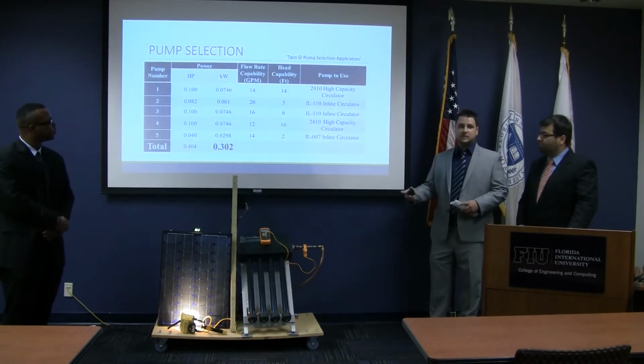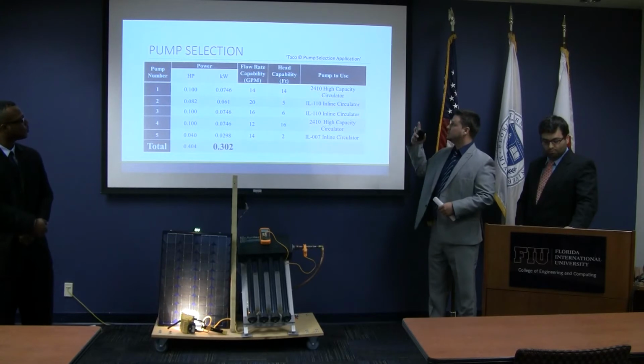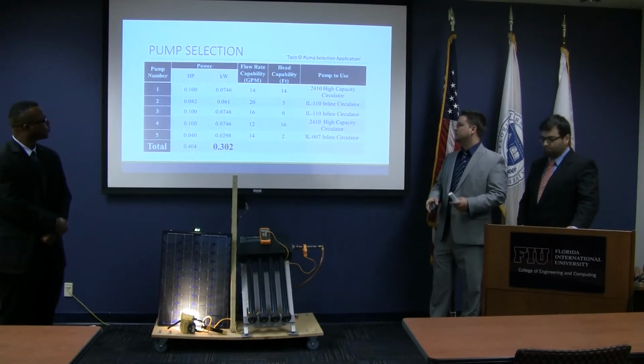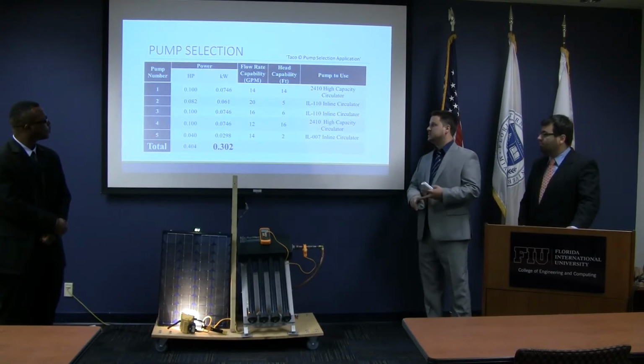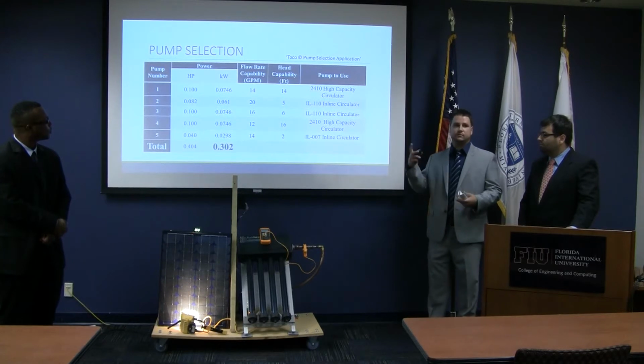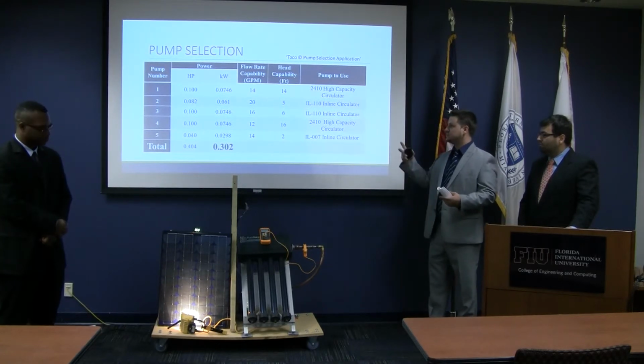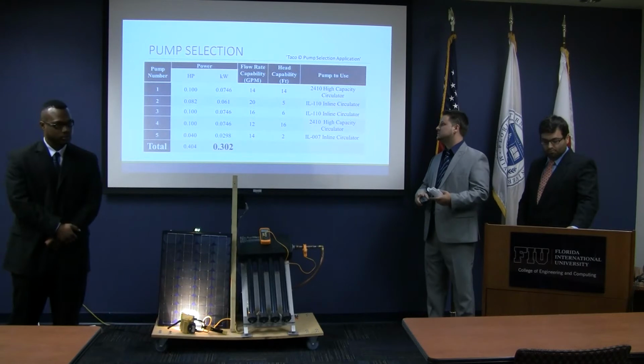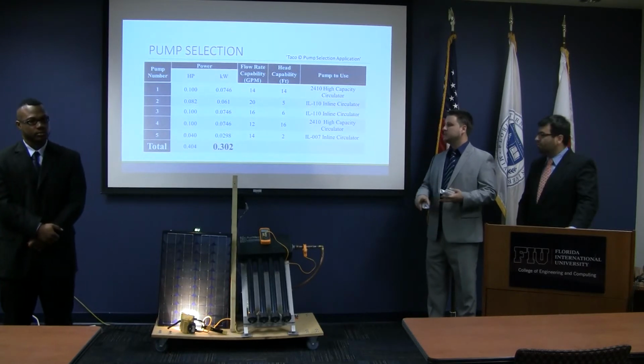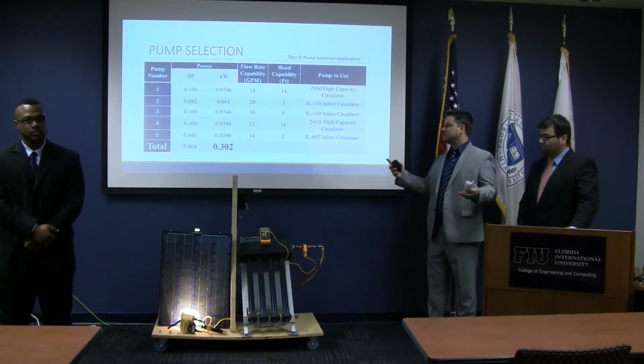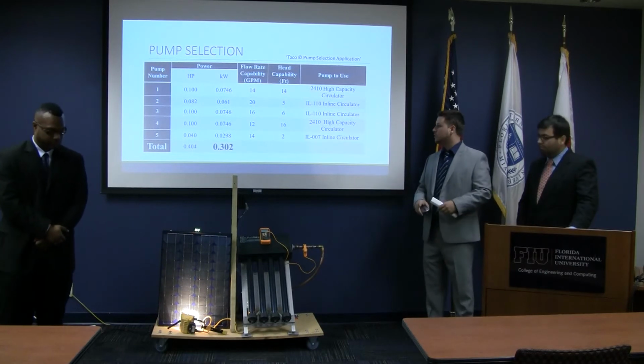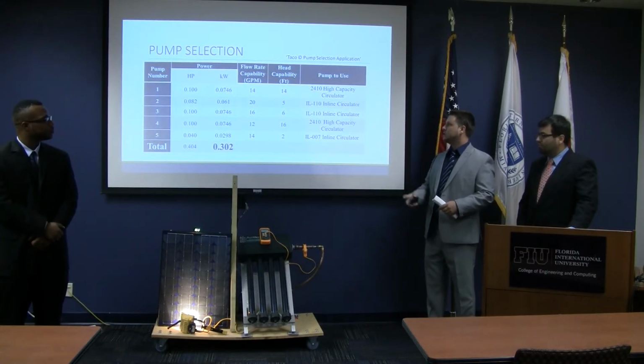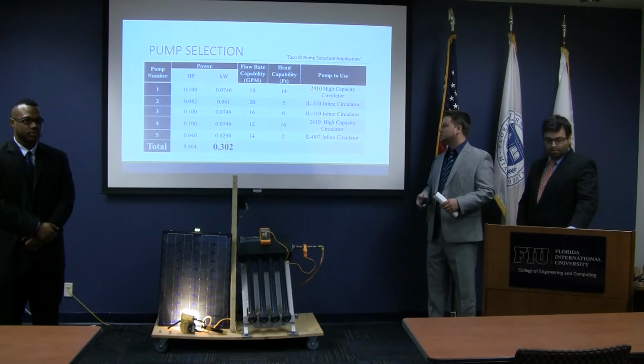And using that most mass flow rate that we found, and using the TACO pump selection application, we chose the capacity that we wanted as far as GPM and also the head foot capability. And these are just the 5 pumps that we found within the system to pump between the evaporator, the condenser, the absorber, and outside the system from the solar water heating. And the total kilowatts that we need for just those 5 pumps is 302 watts.